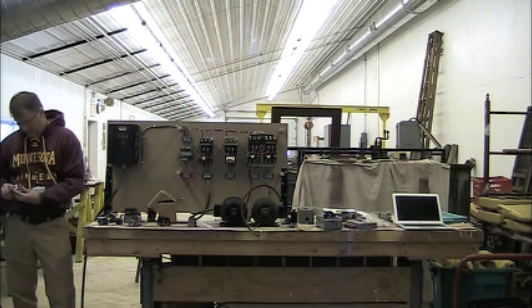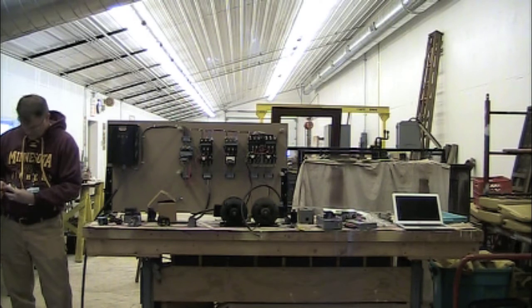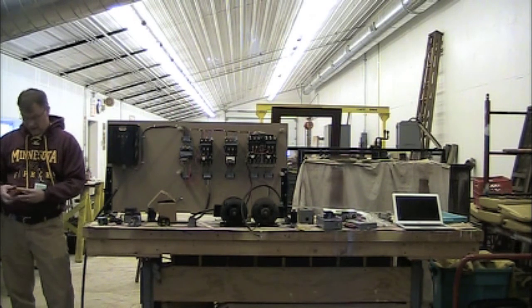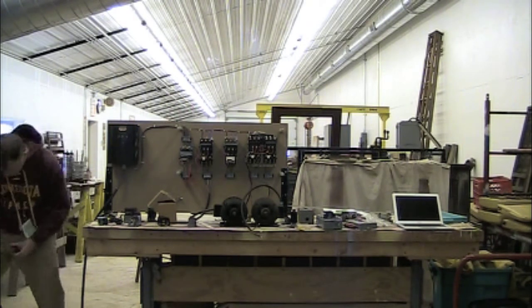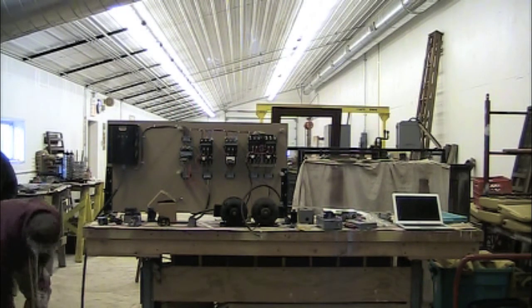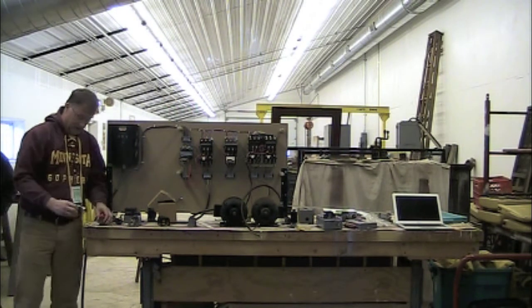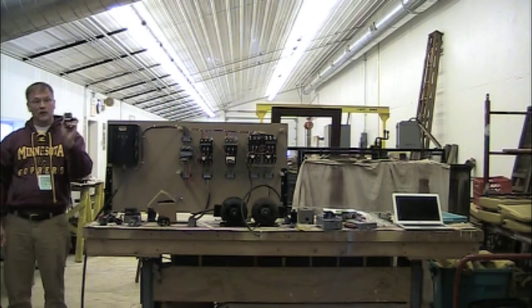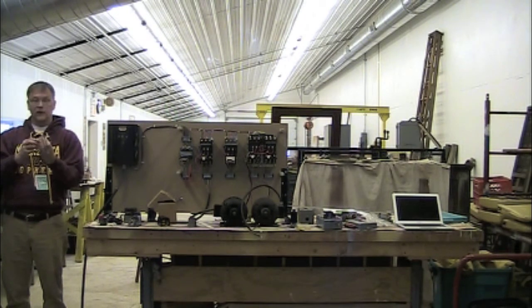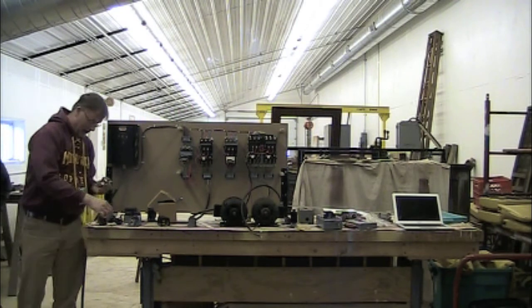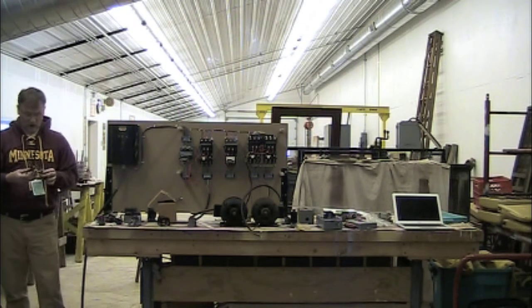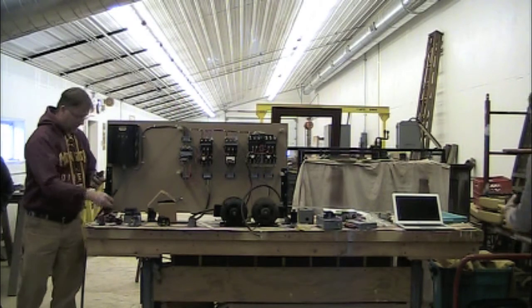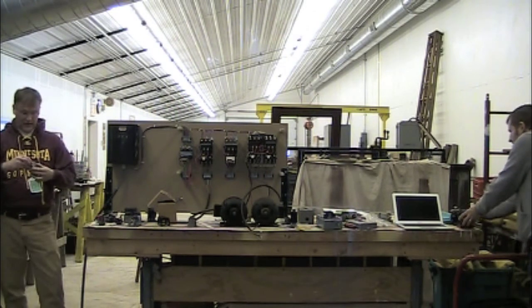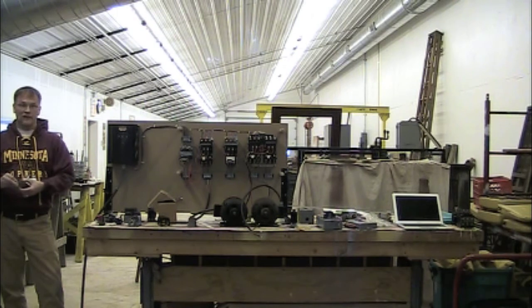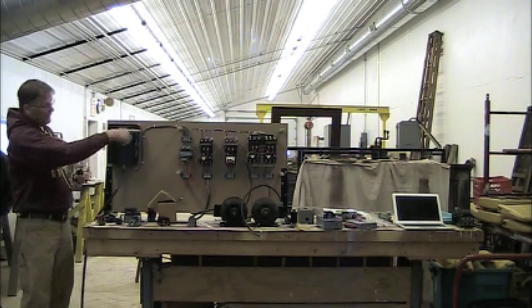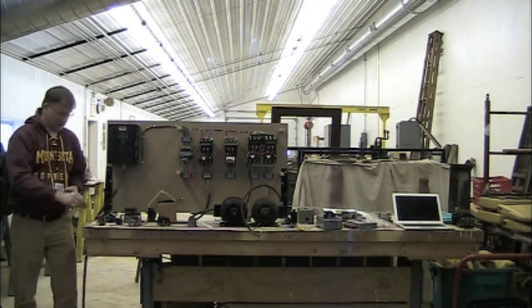And so then that gives me the switching control. So this one is a normally closed contact set. But these things can all be built up. This one has a set of normally closed, normally open. It's also a push-pull operator. And if I need to do something else, if I'm controlling multiple devices, these can be stacked up and you can put multiple decks of them on. So you can have all kinds of different functionality, like doing the two-speed starter over there.